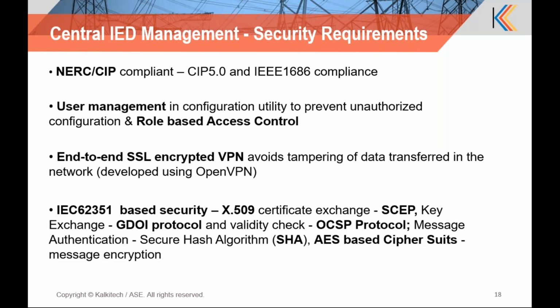So we have a complete software package. IEC 62351 is the basic guideline, and the certificate exchange mechanism is there, using X.509 based certificates, and the Simple Certificate Enrollment Protocol is used for exchanging the certificates. For the validity check, the OCSP protocol is used, and different authentication hash algorithms and cipher suites are used for the encryption mechanism.